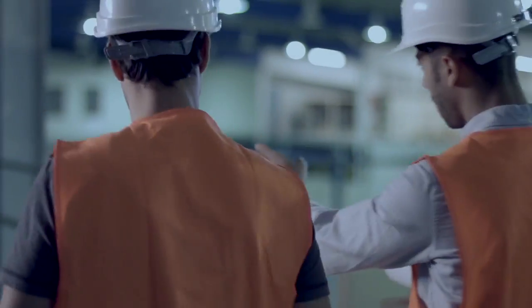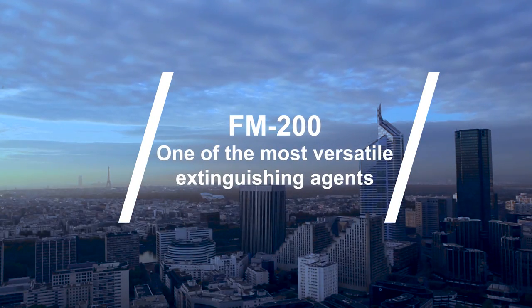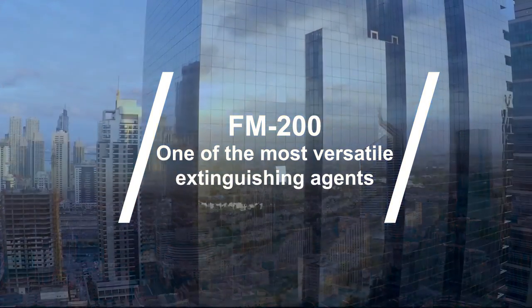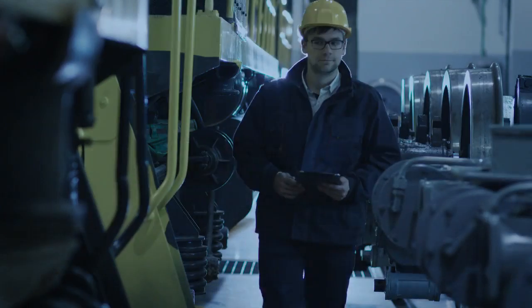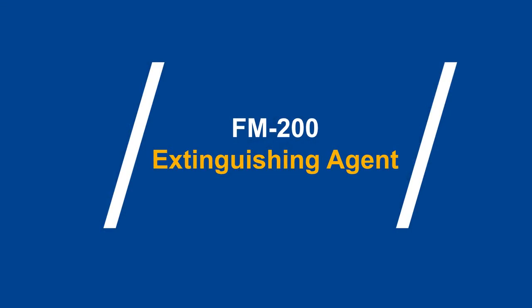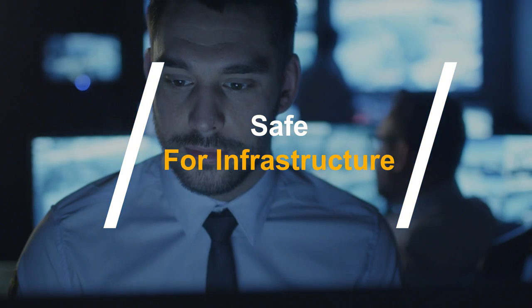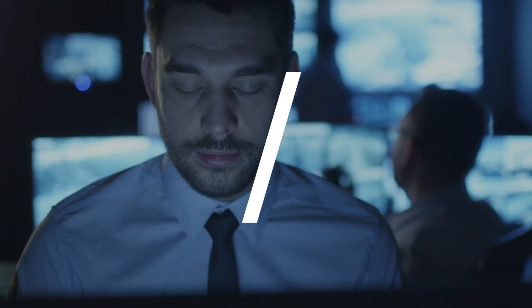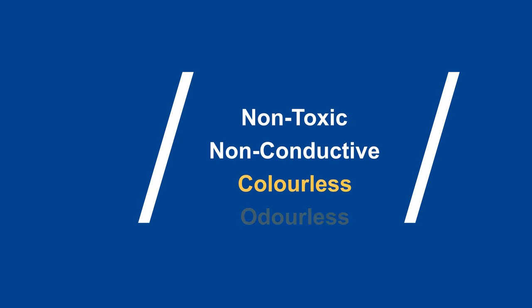The piston flow system uses FM200, one of the most versatile extinguishing agents, and has stood the test of time in the post-Halon era. The FM200 system is designed to provide a concentration of around 7% and will not significantly reduce the oxygen concentration, and with a no observable adverse effect level of 9%, FM200 is designed to be safe for people, and is non-toxic, non-conductive, colourless and odourless.